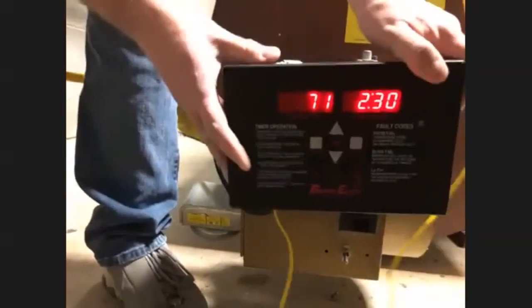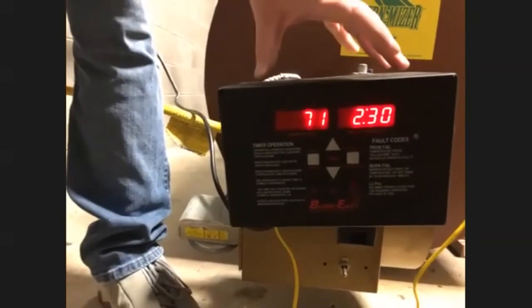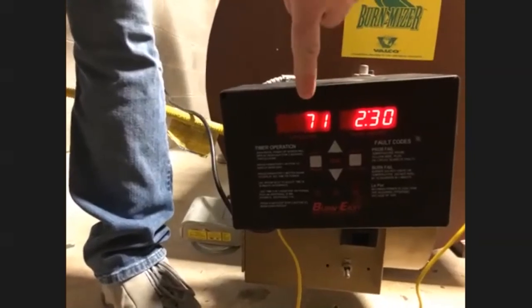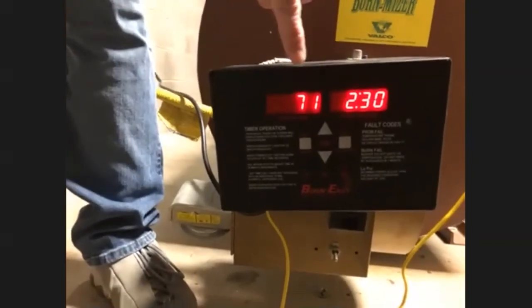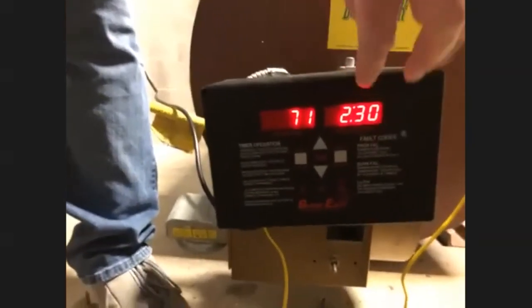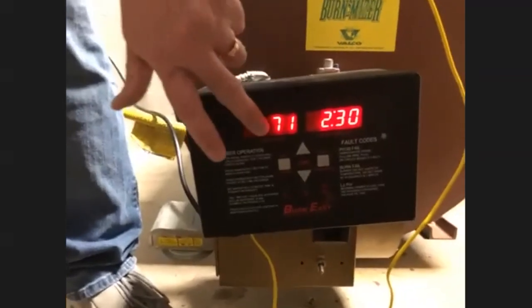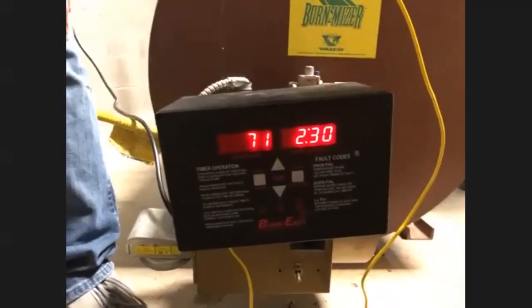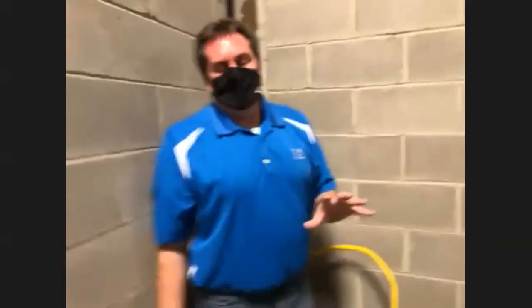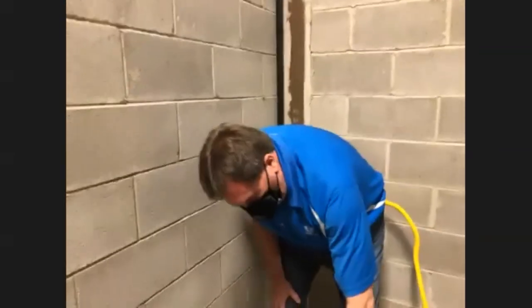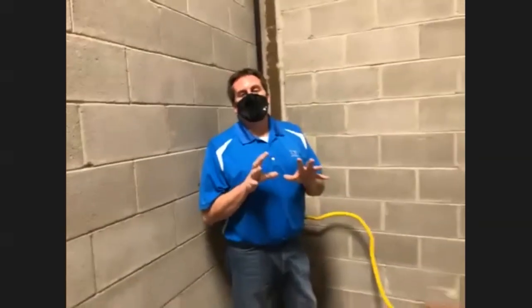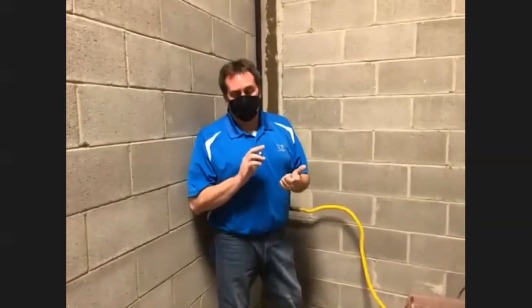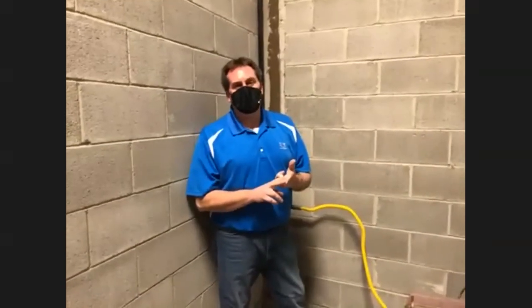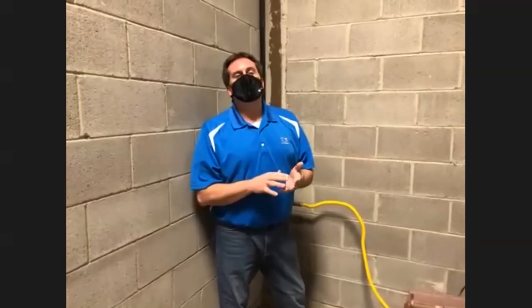I'm gonna stop it for right now. We have things set up where we can adjust things accordingly. And we're showing the temperature, what the temp says inside there. And once things operate, you'll see that temperature rise and you see your timing go down. So that's counting backwards. If the temperature does not rise 10 degrees within the first minute, it will shut off. It says something is not operating properly. And we'll get to the troubleshooting here in a moment. So that's a very easy setup system. Again, you want to make sure you have your proper time period set up. For every 100 pounds you set up for an hour and add 30 minutes.